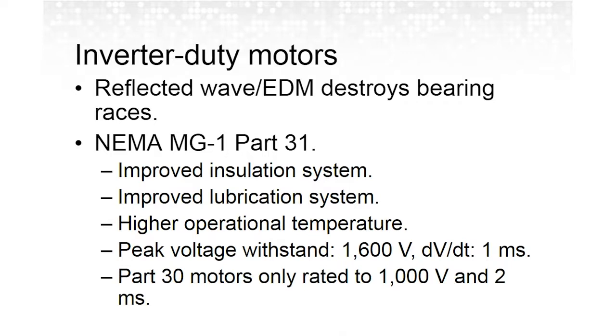Cruising on, we talked about VFDs. Let's go back to motors for a bit. One of the big concerns with use of VFDs is causing damage to the motors that we're connecting to them. It's not unusual where you have a client who will say, I just installed a VFD and I fried my motor a week later.